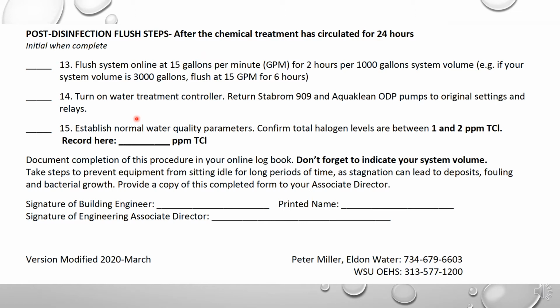You turn back on your water treatment controller, and you want to return that Stabrom 909 and Aquaklean pumps to their original settings where they were when you turned them on. You're going to establish your normal water quality parameters, and you want to confirm that your total halogen levels are between 1 and 2 parts per million, and record that here.